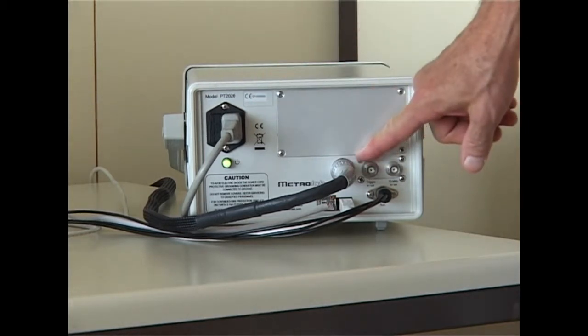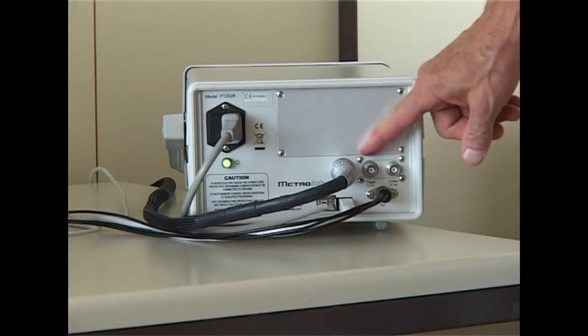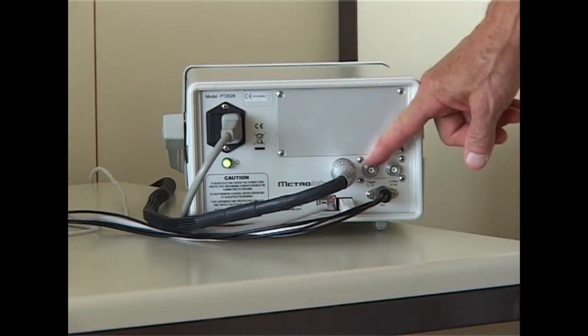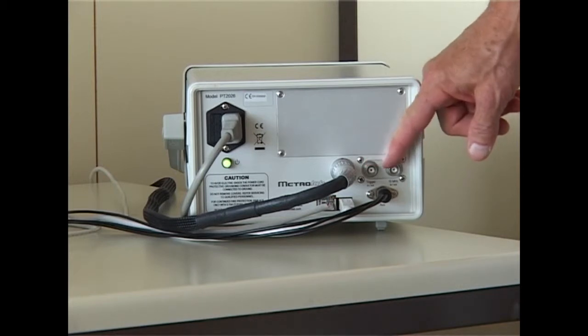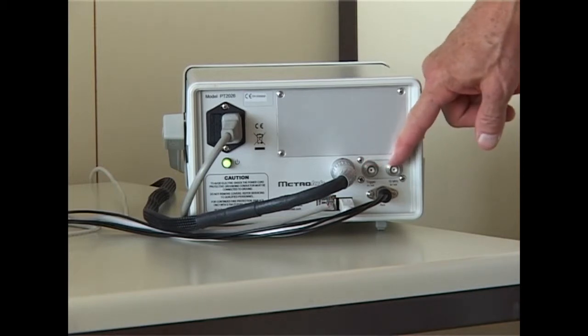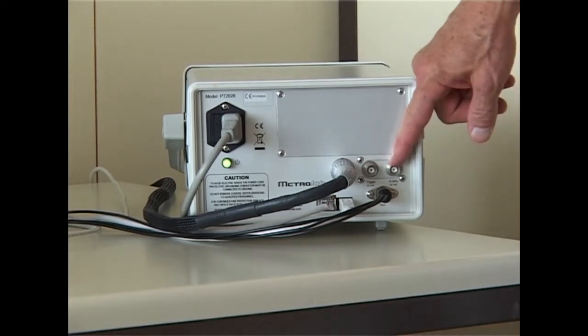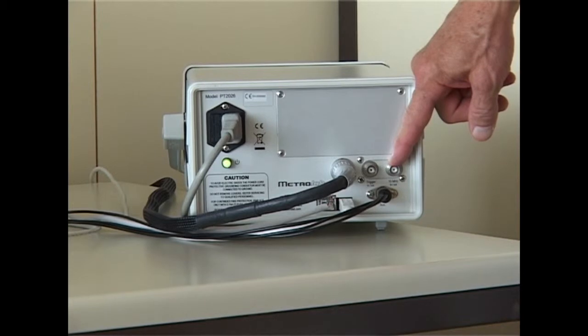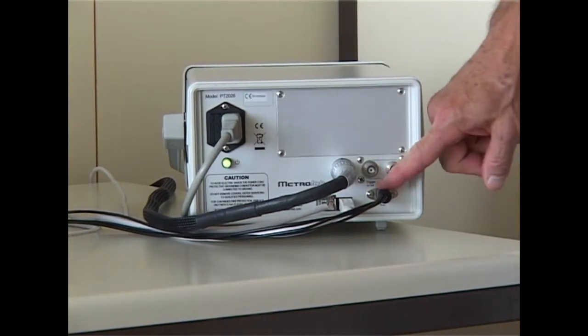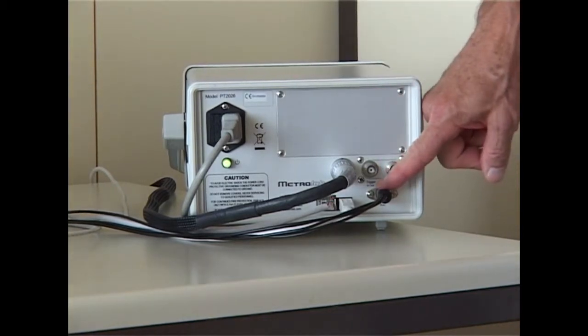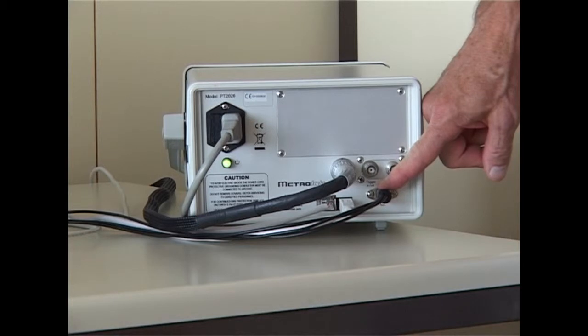Then there are these two BNC connectors. The first one is a trigger input or output, and the second one is a 10MHz reference, also an input or output. Finally this DIN connector allows you to monitor the NMR signal on a scope, just like the PT-2025.